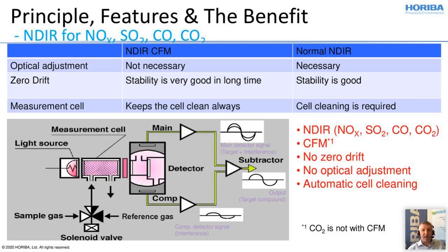The cross-flow modulation type detects the gap of the infrared absorption caused by alternately introducing the sample gas and the reference gas in a period of 500 milliseconds to the same measurement cell. As a detector, the capacitor microphone detector is used. This method enables a time-stable, accurate indication, free of zero drift, as mentioned already. It also realizes easy maintenance, which avoids optical adjustment, as it does not use any rotating chopper, as other general infrared detectors do.